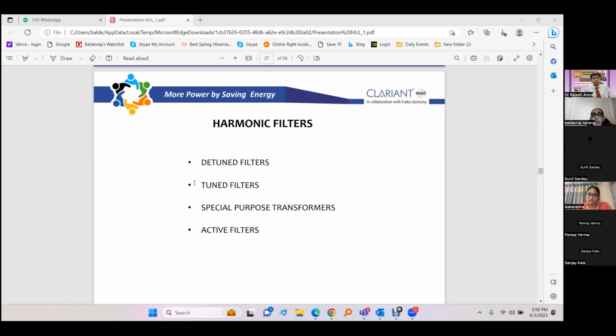And mostly we find that a large percentage of correction can be done with the passive filter itself. In many places we have found that we can correct the entire harmonic filtration with passive only, but it is not always possible. So sometimes we have to use active filters also. With an active filter, we can have a very fine correction as well. Then I'll come to that in the next slide. So we have seen tuned filters, detuned and tuned, it's the same thing. Then for the third harmonic, we have a special purpose transformer, that is a zigzag transformer.